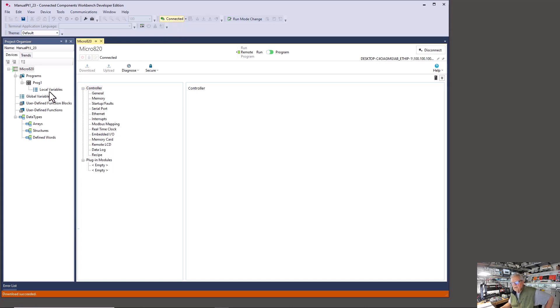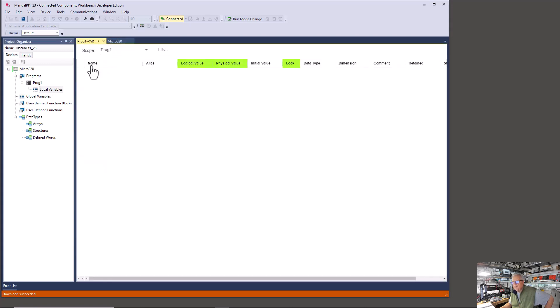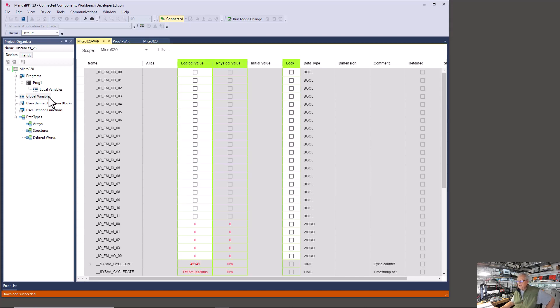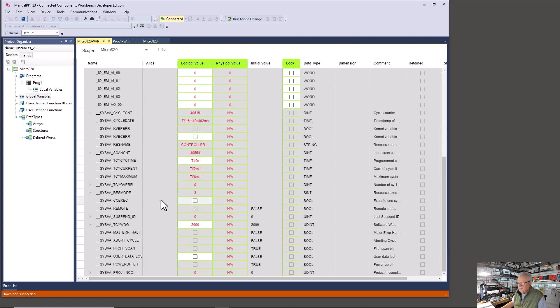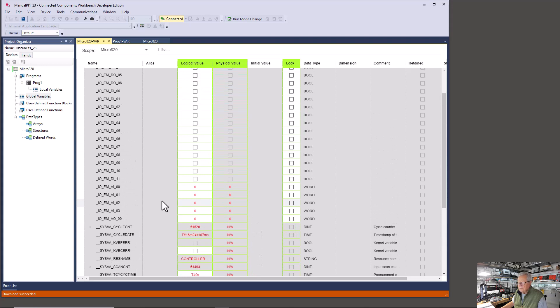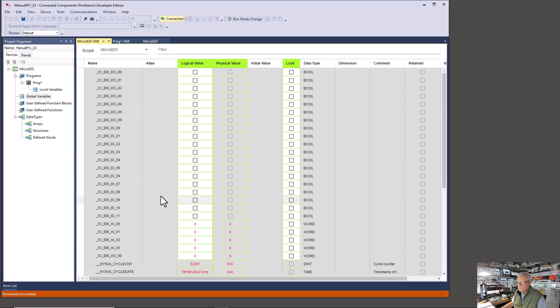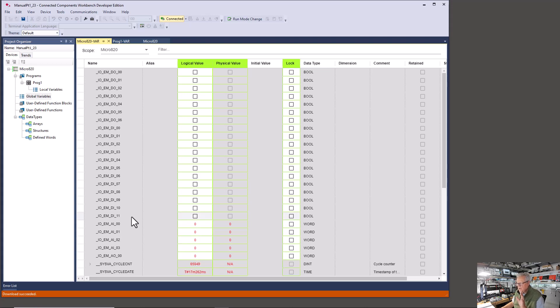Let's open up the local variables — you see there's nothing there — and the global variables — there's nothing there either, but it looks completely different. You can see some values changing in the system variables. These are variables the system provides you and you can access them; most are read-only, some are writable. What we're particularly interested in are the IO variables. Some say 'IO EM' — EM for embedded, meaning they're in the little plastic box with the processor. Some say DO for digital output, some say DI for digital input. We're going to stay away from analog for right now.